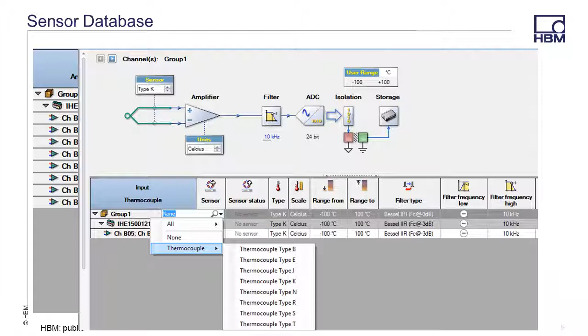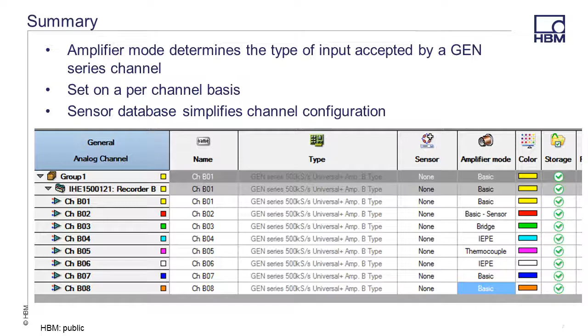In summary, the amplifier mode of a Gen series channel determines what type of input signal can be measured. Some Gen series modules support a wide range of sensor types, and others can only accept one or two. The mode can be set on a per-channel basis. There are separate pages in the settings sheet for each input type, which helps to simplify the channel setup for the user. The sensor database feature of Perception can be used to automatically configure a channel to work with a specific sensor.